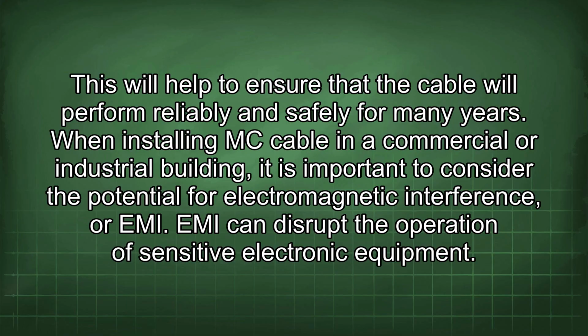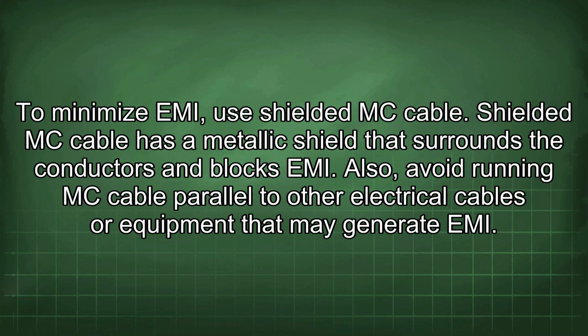When installing MC cable in a commercial or industrial building, it is important to consider the potential for electromagnetic interference, or EMI. EMI can disrupt the operation of sensitive electronic equipment. To minimize EMI, use shielded MC cable. Shielded MC cable has a metallic shield that surrounds the conductors and blocks EMI. Also, avoid running MC cable parallel to other electrical cables or equipment that may generate EMI.